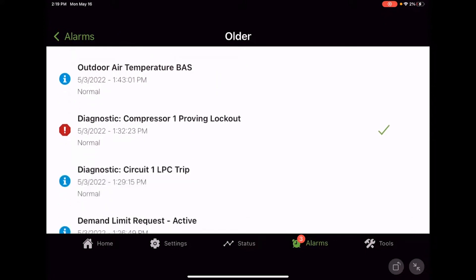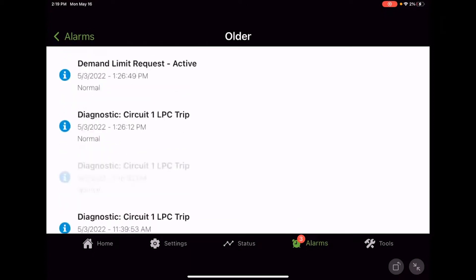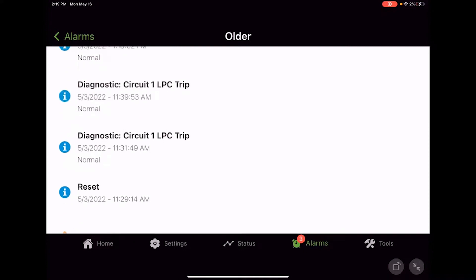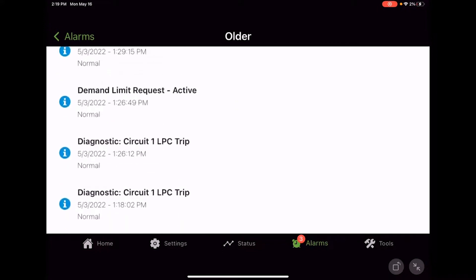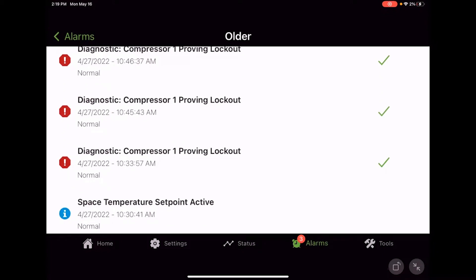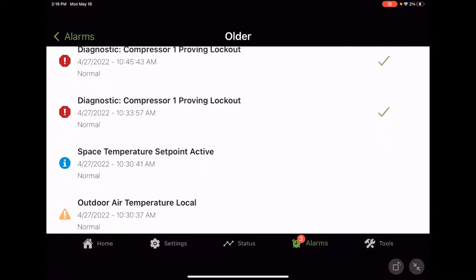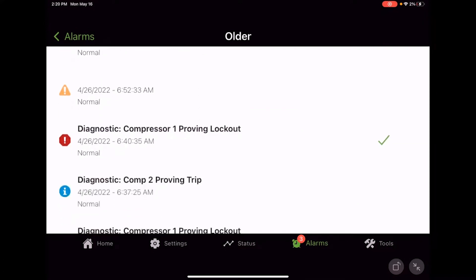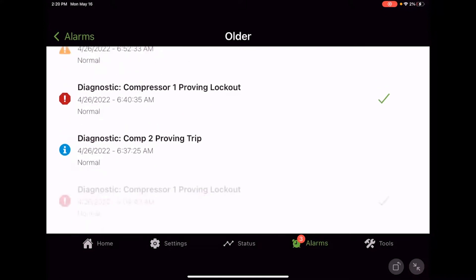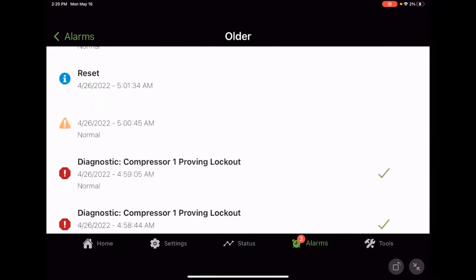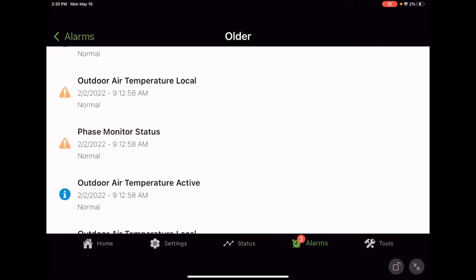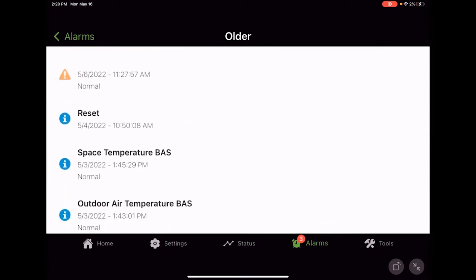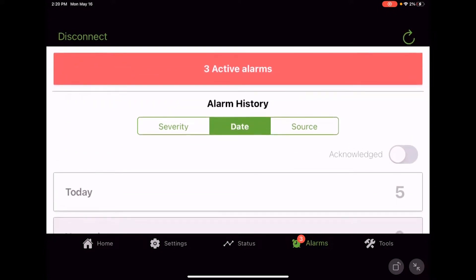There's that diagnostic, compressor one proving lockout on May 3rd. We see a green check mark. That means it has been acknowledged. And then we've got some demand limit requests. We got some more of that low pressure going back to normal. Oh, there's these proving lockouts, proving lockouts, proving lockouts while that low pressure control. What do we got going on? Or why was that proving lockout not making on April 27th? So we can definitely go in, it looks like April 26th, we had some issues with it too. And again, the green check marks on the right hand side here, that alarm or that diagnostic has been acknowledged. Okay. So again, it's really good. We can use this to go through and troubleshoot. And it gives us a nice clear language way of determining where to start, maybe where to go look at our troubleshooting.